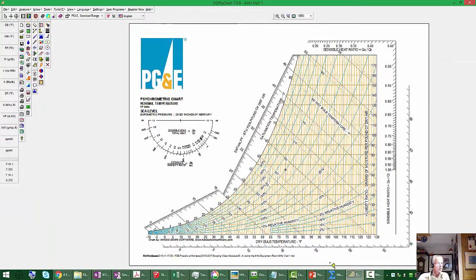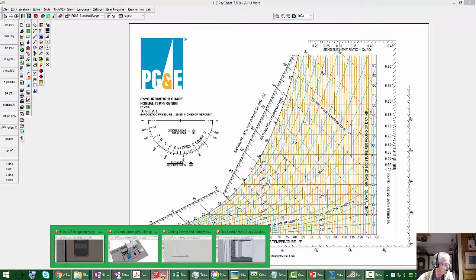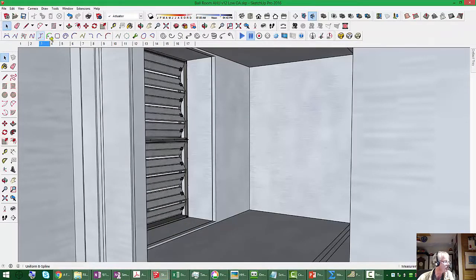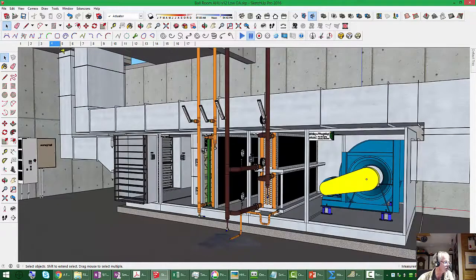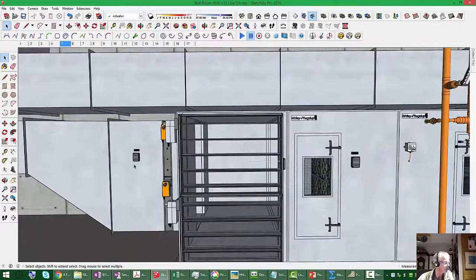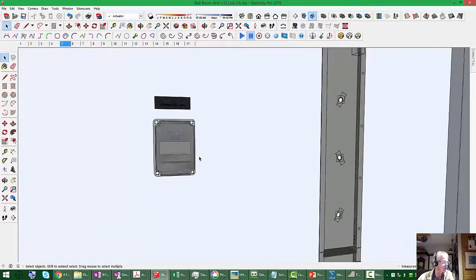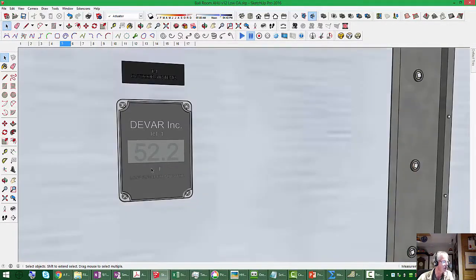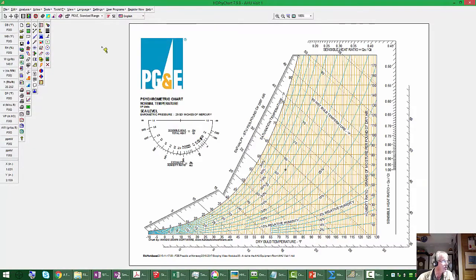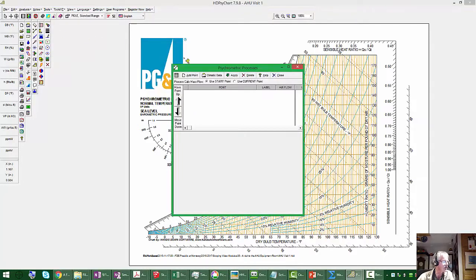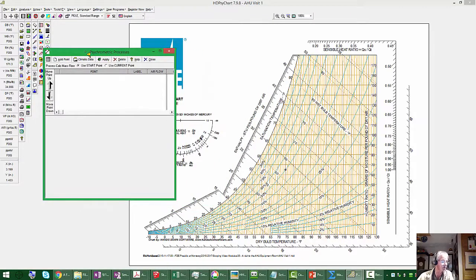Okay, so what do we know? Well, we know that outside, what temperature was it outside? Let's go back. We have an outside air temperature transmitter on this unit, right back here. This is actually where the signal in the central plant's coming from. It's a retransmit off this device. So it's 52.2 outside. Okay. And to plot a point on the psych chart, you need to know both a temperature and some moisture condition. And since it's foggy, that lets us imply that the moisture condition is 100% relative humidity.